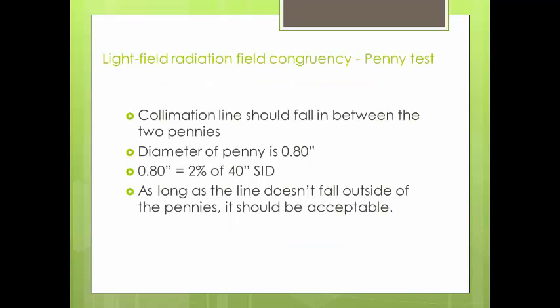To determine whether or not your penny test is acceptable, the collimation line should fall directly between the two pennies. The diameter of a penny is 0.8 inches, which happens to be 2% of a 40-inch SID — which is where we need our light field radiation field to be. As long as the line doesn't fall outside of the pennies and you can see only one penny and a portion of the other, your test is acceptable.